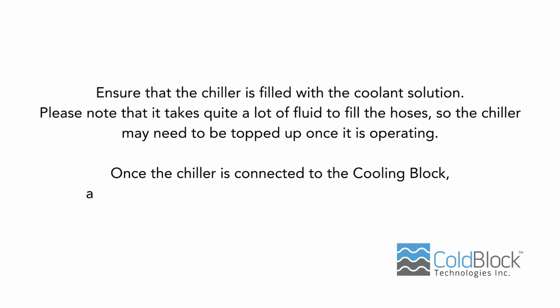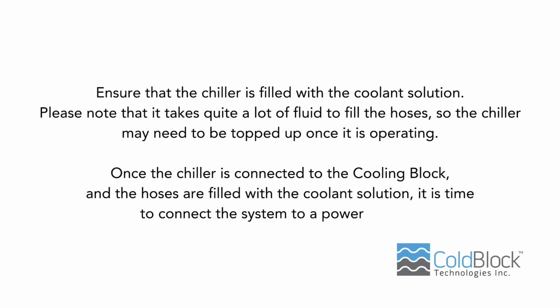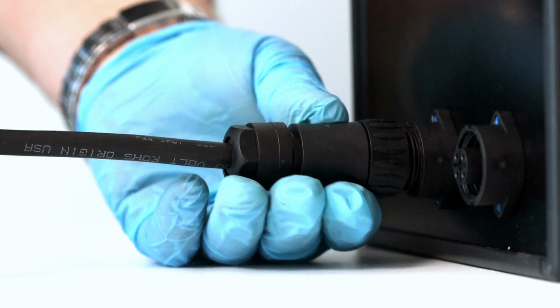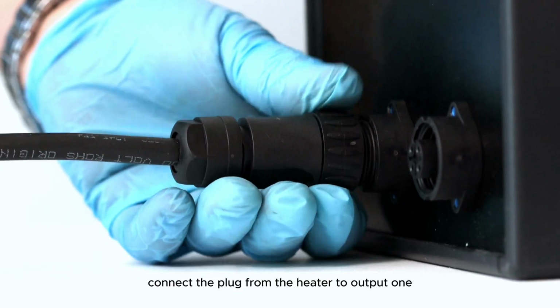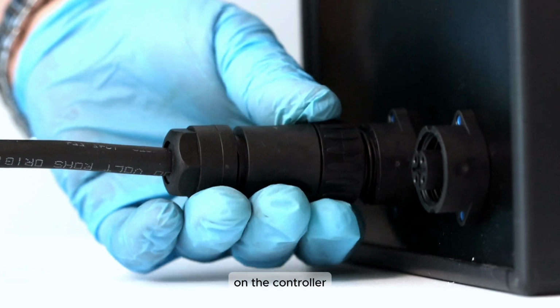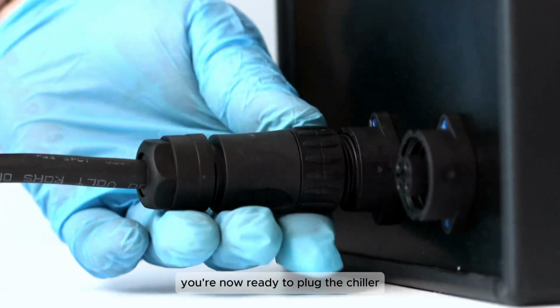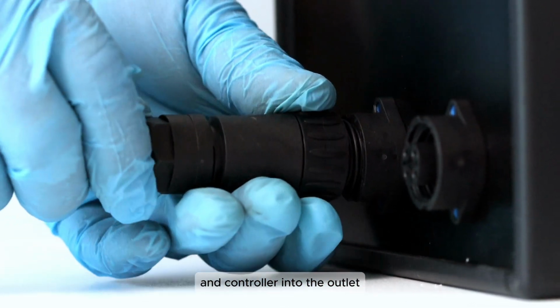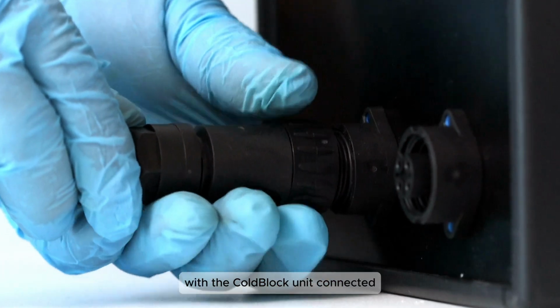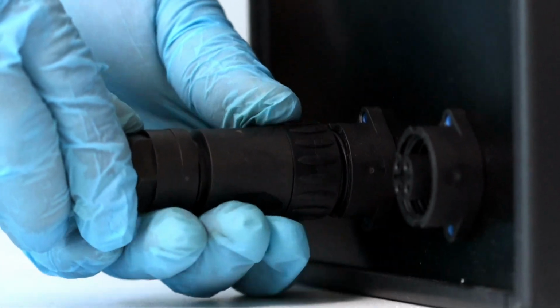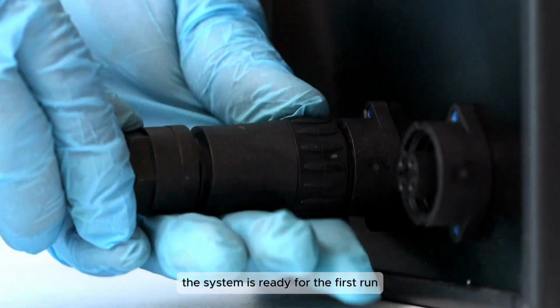Once the chiller's connected to the cooling block and the hoses are filled with the coolant solution, it's time to connect the system to a power source. Connect the plug from the heater to output 1 on the controller. You're now ready to plug the chiller and controller into the outlet. With the ColdBlock unit connected and the controller plugged in, the system is ready for the first run.